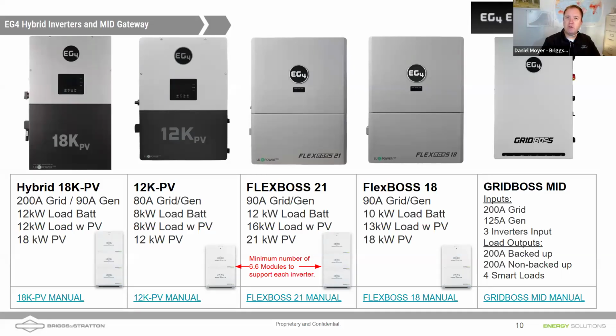Now, on the bottom, we're looking at our 6.6 stacking battery. Each battery module is 6.6 kilowatt hours. A full stack, which would be 3 modules in a single stack, that's the most you can do in a single stack, comes in just under 20 kilowatt hours, which is perfect for those NFPA 855 requirements of having increments in 20 kilowatt hours, and then cumulative capacity limits for certain areas of the house, like the garage or the basement. We get as close to that 40 or that 80 kilowatt hour threshold as we can.